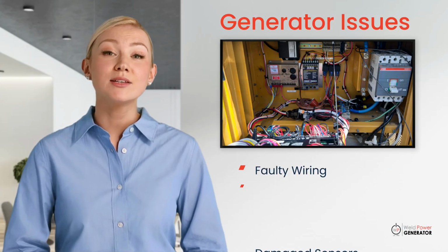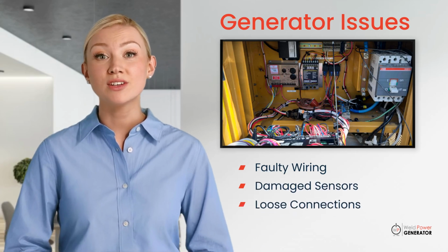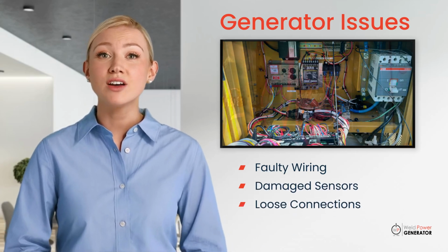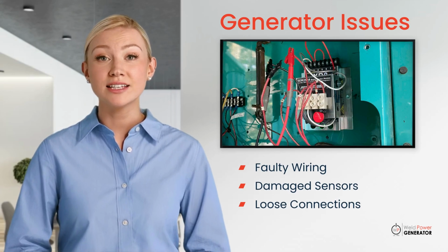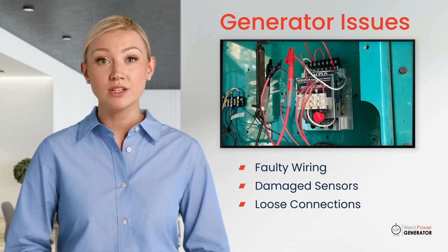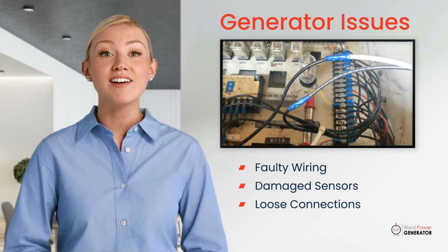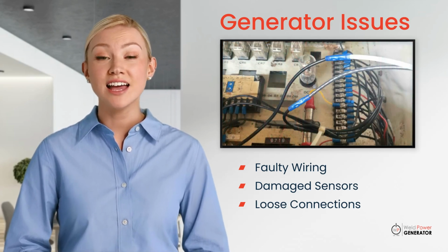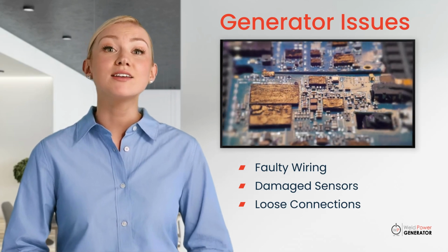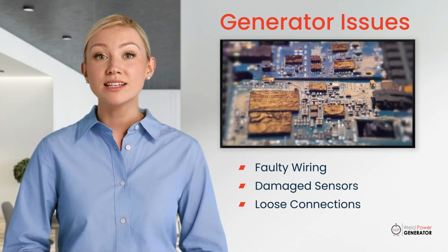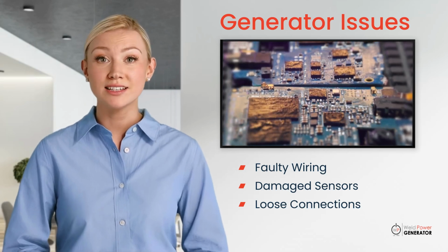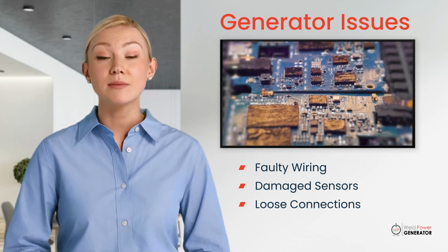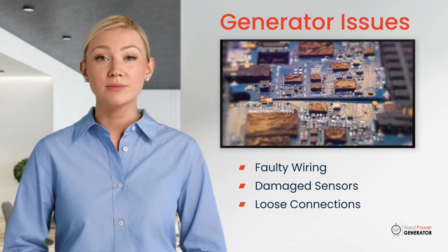Faulty wiring, damaged sensors, or loose connections within the generator's control panel can cause incorrect readings, tricking the system into thinking there is a power outage. A thorough inspection of wiring harnesses, voltage sensors, and control circuits can help diagnose and resolve these issues. These problems can start for various reasons, such as corrosion, rodent damage, water damage, and more.